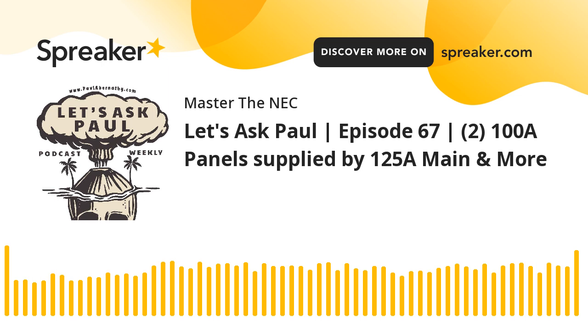Thank you very much. All right, so the premise here is that we have to look at the breakdown of what we're trying to do here. It's very common for us to have a panel where the breakers itself will exceed the rating of whatever the main breaker is of the panel. We see this all the time, right? This is a common thing we see and perfectly fine, acceptable practice. What we have to remember is that the feeder breaker is protecting the feeder. And so that's the key.